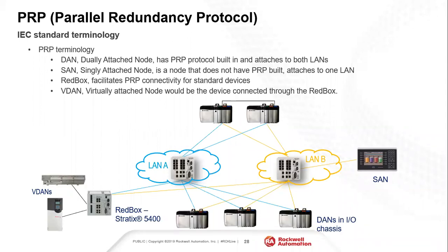So the device level ring stuff, we're down to version 20 if we're doing redundancy on that side, whether we're talking about version 20, 24, 31, or 32 now with redundancy. But on this side, if we're doing parallel redundancy and you need redundant ControlLogix, we'd be at minimum version 31. Any questions? So one of the things, if you guys run across this, a lot of the times what I end up doing is doing a comparison between both.